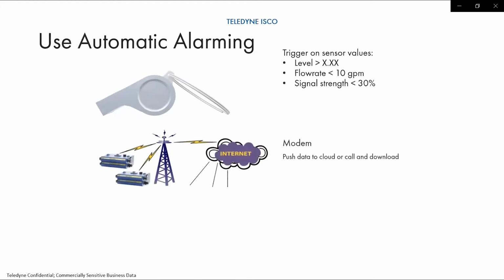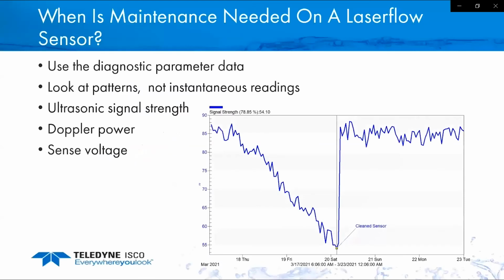How you can do that is use a modem: Modem, Ethernet, IP address, send that data out to the cloud or have it call you. If you have a modem on your equipment, it can automatically send you a text message, or you can use your SCADA system to send out your alarms via Modbus or analog. However you have to do it, use the tools available to you for your diagnostics to determine when you should go out to those sites.